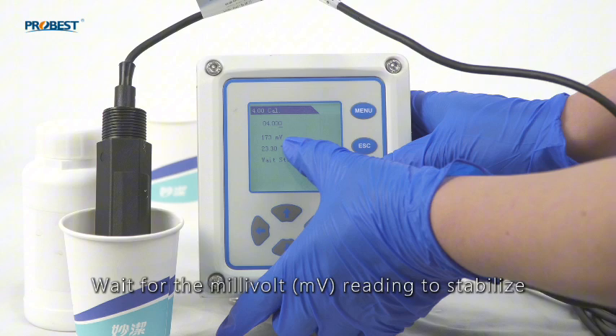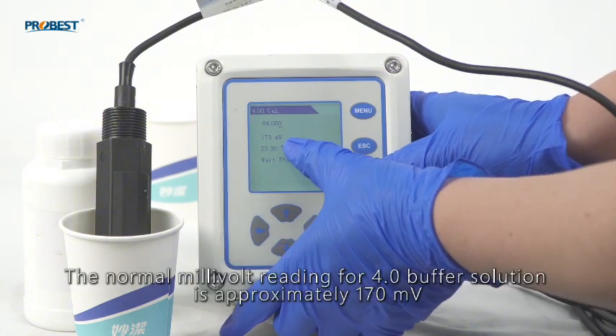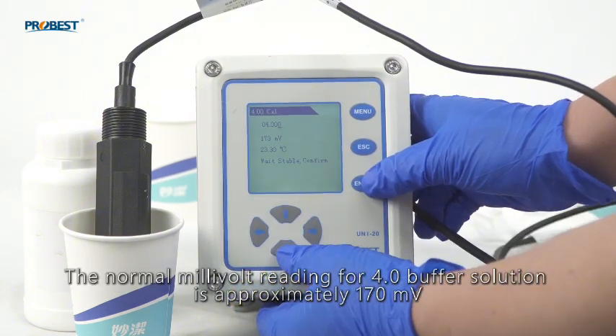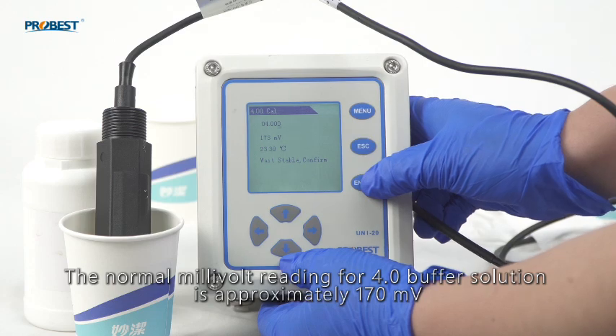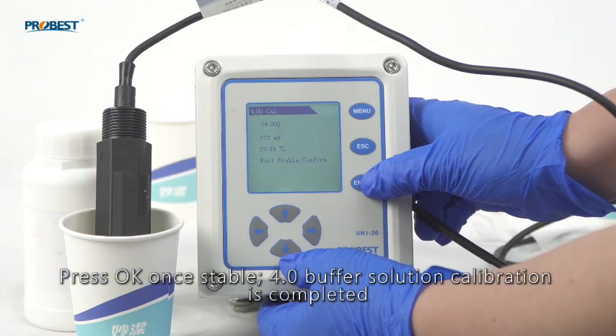Wait for the millivolt mV reading to stabilize. The normal millivolt reading for 4.0 buffer solution is approximately 170 mV. Press OK once stable. 4.0 buffer solution calibration is completed.